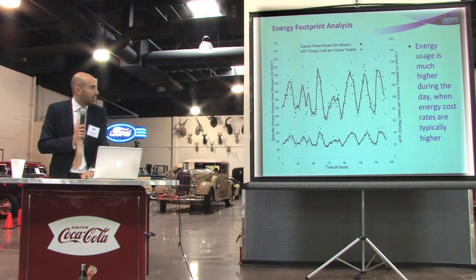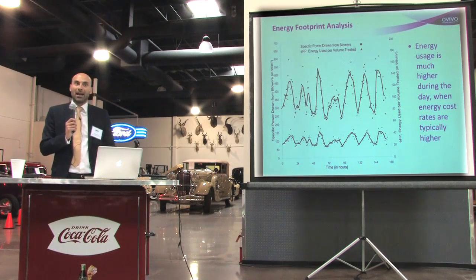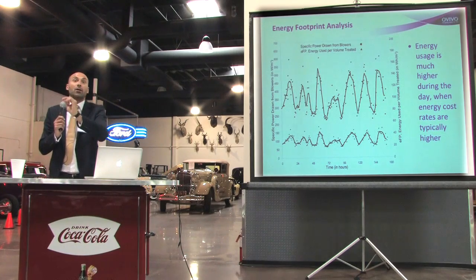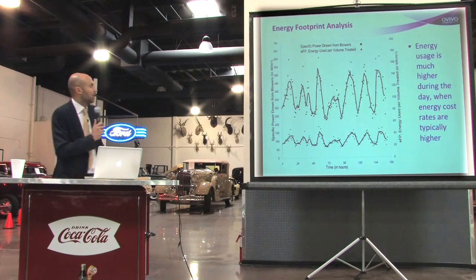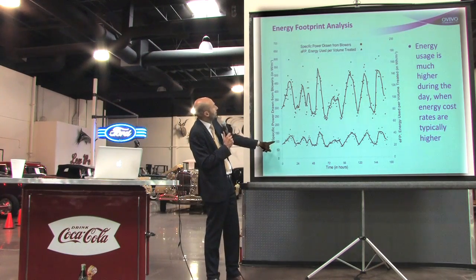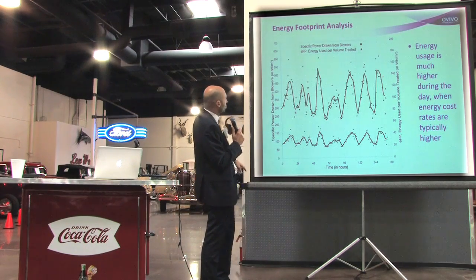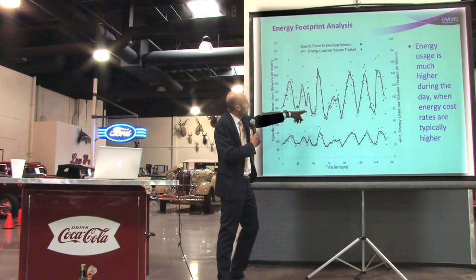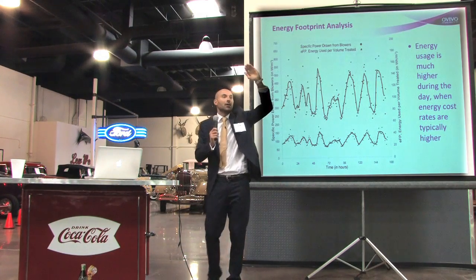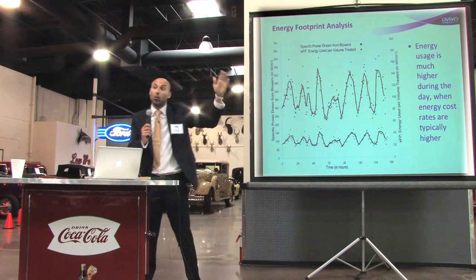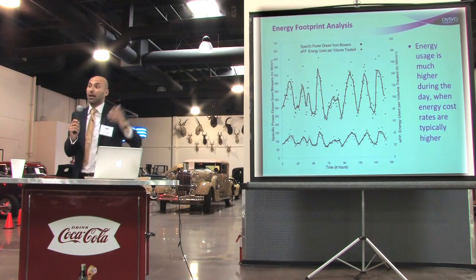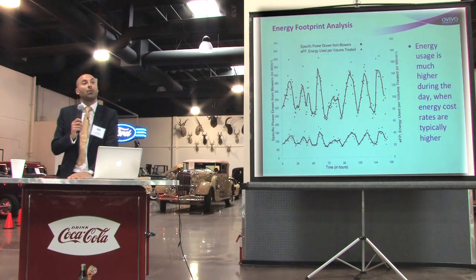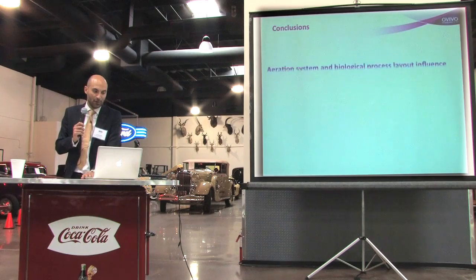Using our automated analyzer feeding the blower curve in a spreadsheet, we compute actual power drawn and cumulative energy consumption over 24 hours. The power peaks are large and can trigger a higher demand charge that you carry for a full quarter. You want a strategy to equalize flow, cap power draw, or tune your operational response dynamically — and this type of analyzer lets you quantify and make the business case for it.